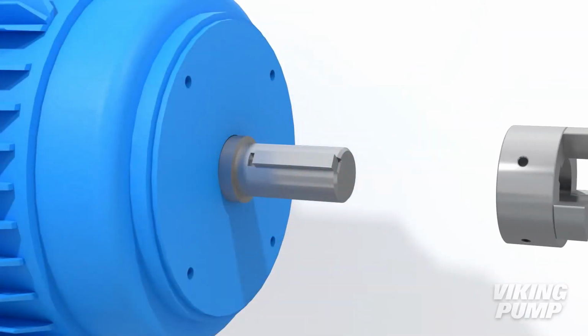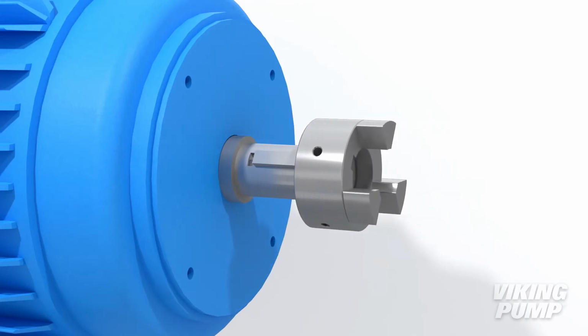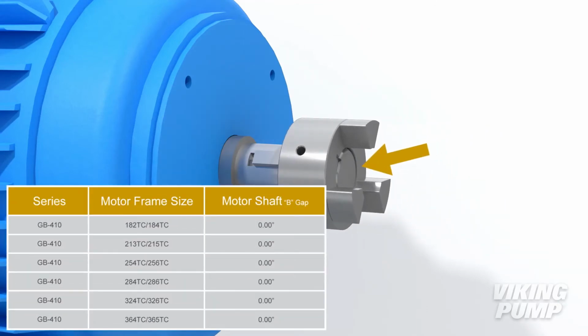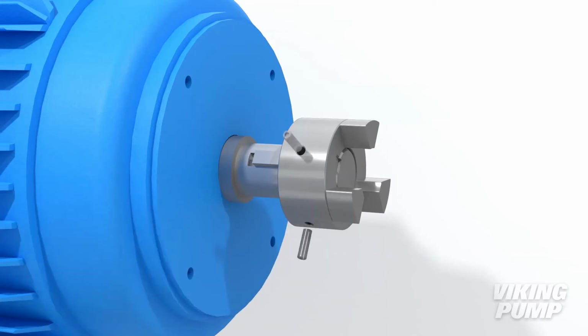Now, place the motor coupling hub on the motor shaft and key. Make sure to follow the coupling gap dimension requirements. These values can be found in the technical service manual. Then, tighten the coupling hub set screws.